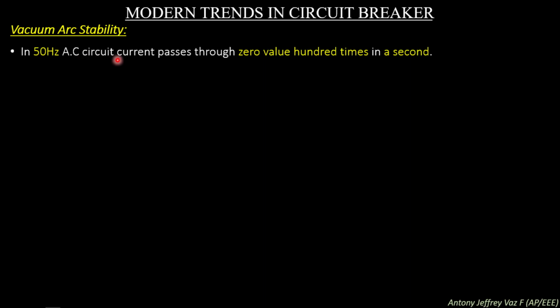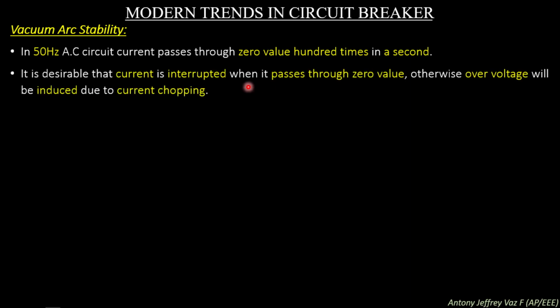In a 50 Hz AC circuit, the current passes through zero value 100 times in a second. It is desirable that current is interrupted when it passes through zero value, otherwise overvoltage will be induced due to current chopping. So, in a vacuum circuit breaker, when the current passes through zero value, the arc present in vacuum will be interrupted on its own. At this time, the current chopping effect should not be increased. So, the microscopic projections which are the cause of creating vapors, and these vapors, should be removed by the vacuum circuit breaker to stop the arc and to stop the current chopping effect.